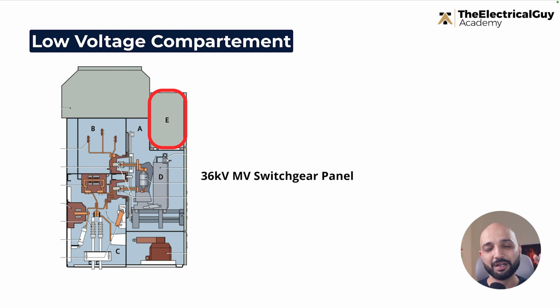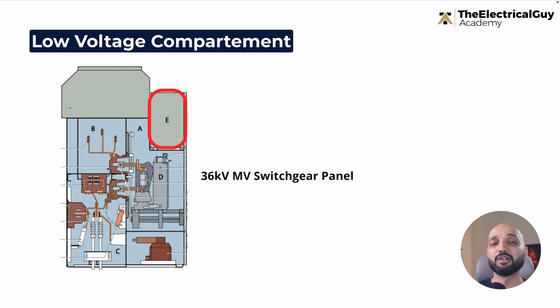And that is also the reason why it is called the low voltage compartment, or sometimes people also refer to it as the metering and relay chamber. They operate on a much lower value, almost in all cases less than 1000 volts, right? So the operating voltage, the control voltage may vary from project to project, customer to customer, but general ratings you can consider 110 volt DC, 220 volt DC, 48 volt DC. Now I've done a dedicated video where I explain why the low voltage compartment only operates on DC supply. So if you're interested, you can definitely check that out. So that is the reason it is called the low voltage compartment, because it works on low voltage supply only.